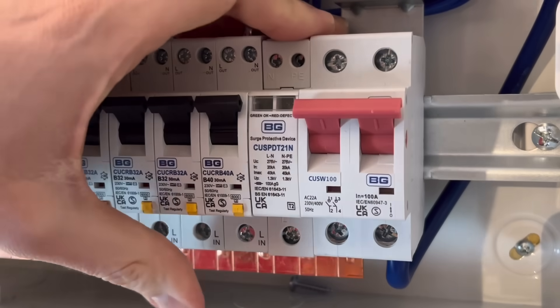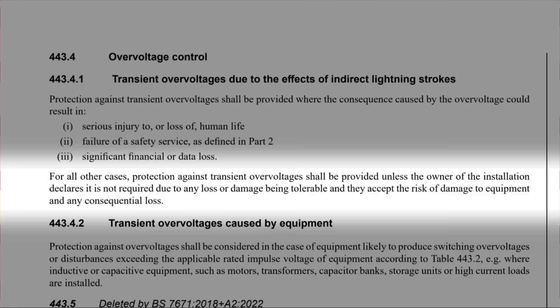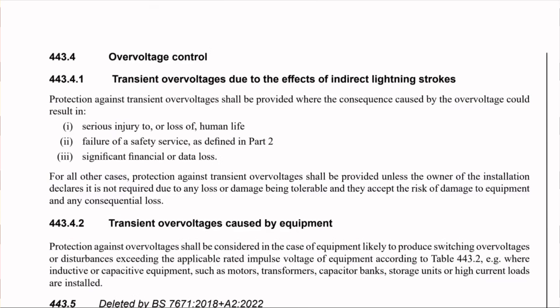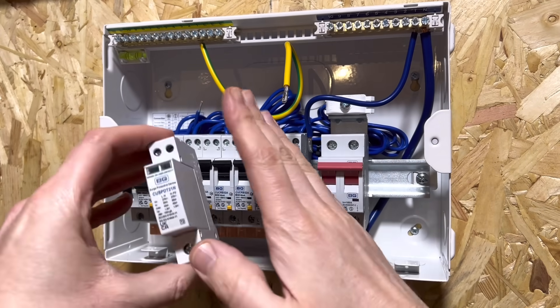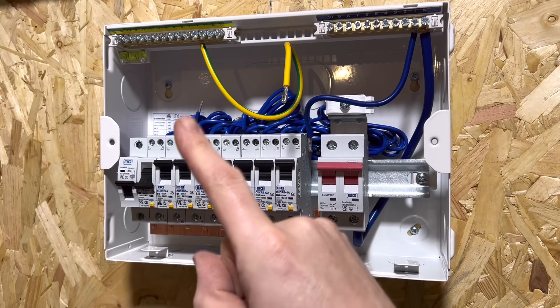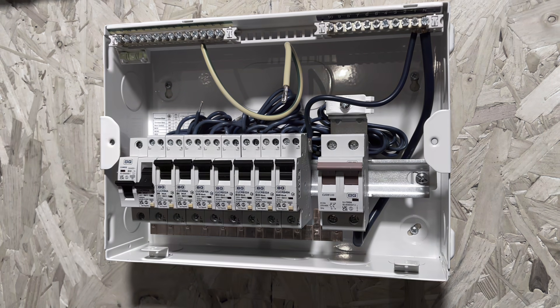But there's a little more to this reg as it concludes. For all other cases, protection against transient overvoltages shall be provided unless the owner of the installation declares it is not required due to any loss or damage being tolerable, and they accept the risk of damage to equipment and any consequential loss. So basically, if surge protection is required for any of those three points, then it must be installed - there's no way around it. But if those conditions don't exist, then you must install surge protection unless the owner of the installation tells you they don't want it and are happy to accept the risk.